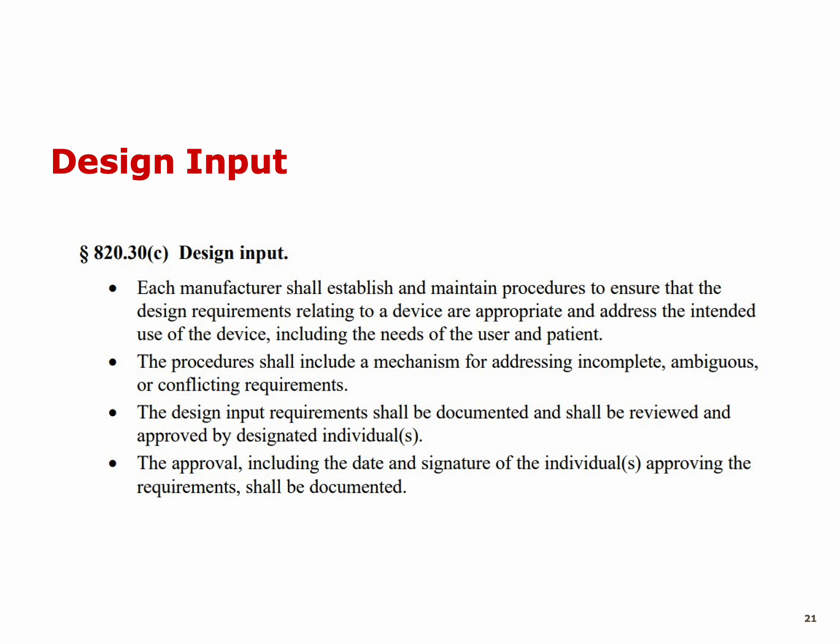So as per 21 CFR Part 820.30, related to the design input, each manufacturer shall establish and maintain procedures, so these are SOPs, to ensure that the design requirements relating to a device are appropriate and address the intended use of the device, including the need of the user and patient. Here you understand that for each device, you may have a set of SOPs. And in this case, we are going to have hundreds of SOPs if you have tens of devices, but we have to be in full compliance with the regulations.